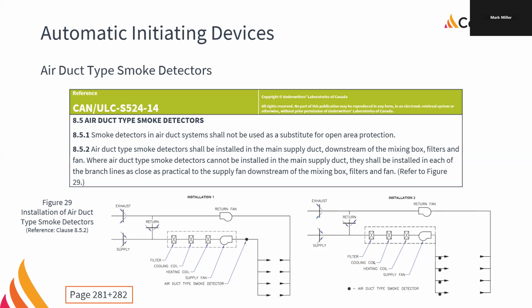The downside, of course, is often the mechanical engineers don't think about this. We have an air handling unit on the roof, and the ductwork comes straight down and then branches off two or three or four ways immediately. And so we don't have any space to put the duct smoke because we need a fairly long straight length of ductwork. The rule is generally 6 duct widths. Okay, so if it's a 2 foot wide duct, we need to be 12 feet downstream of any bend or turn or change in size or fan or anything like that. So getting that kind of distance can be difficult.